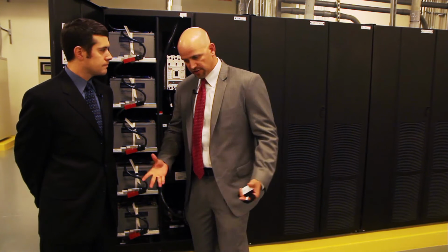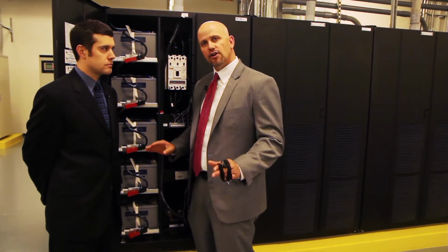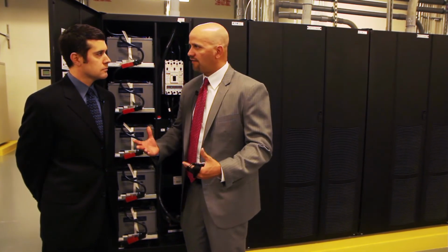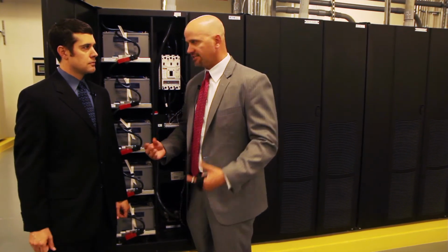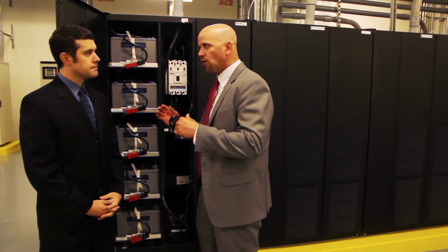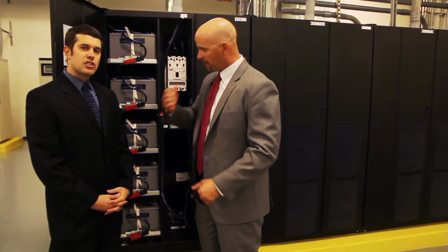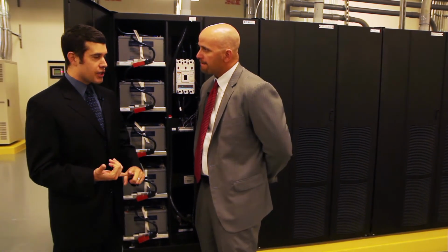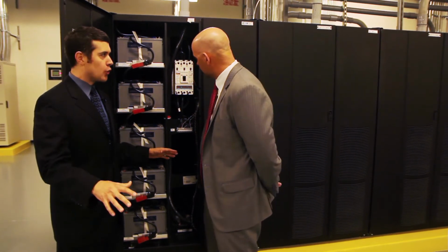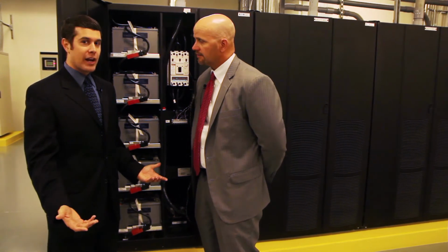I'll tell you what else is very cool. In the last segment, you saw the UPS at the bottom. And what we've just learned is they never do that in a data center. Why? Because that UPS could actually catch on fire or spill or contaminate the data center. In this power room is where all the power's conditioned. The UPS is here, ready to go. So if you were to have any sort of explosion, any sort of drain of acid or anything like that, here it would happen in a controlled environment. Someplace else it would happen next to a bunch of other equipment, which might not be a good thing.